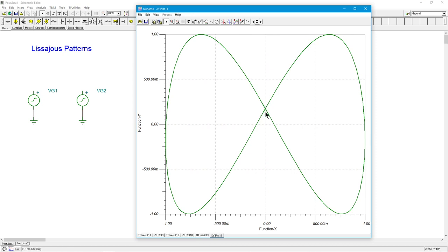Womp, right? See, it's not as high. So when it's right there at zero, you know it's the exact phase. And as it goes out, this way or this way, you know that the phase is getting worse and worse. They're getting more and more out of phase, along with the frequency shift, all right?